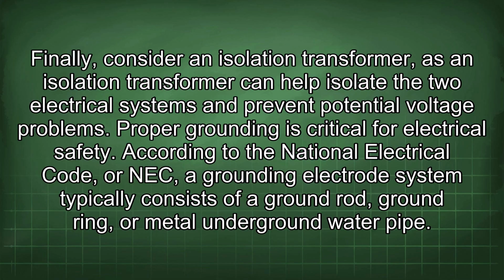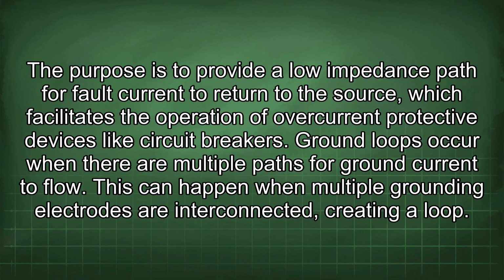According to the National Electrical Code, or NEC, a grounding electrode system typically consists of a ground rod, ground ring, or metal underground water pipe. The purpose is to provide a low impedance path for fault current to return to the source, which facilitates the operation of overcurrent protective devices like circuit breakers.